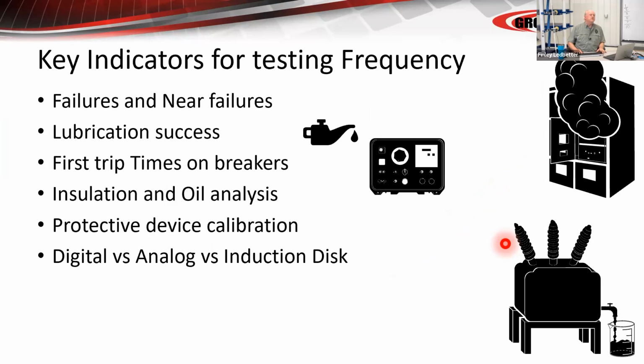You know, key factors or indications on frequency is, have you had any near failures? Have you had any near misses? Have you had any instances where maybe the breaker didn't operate correctly, but it was never called upon to do so? So essentially you don't have a failure.